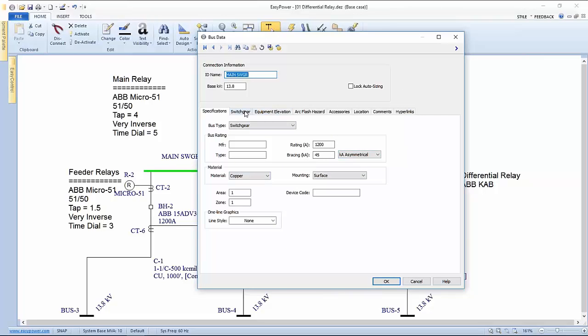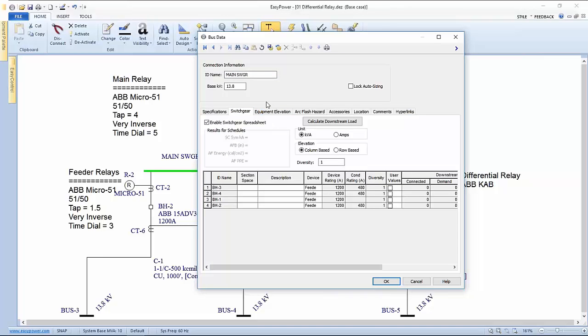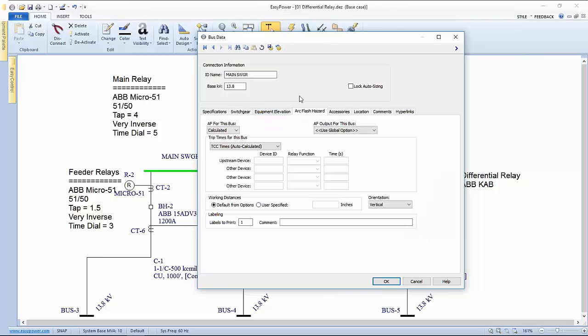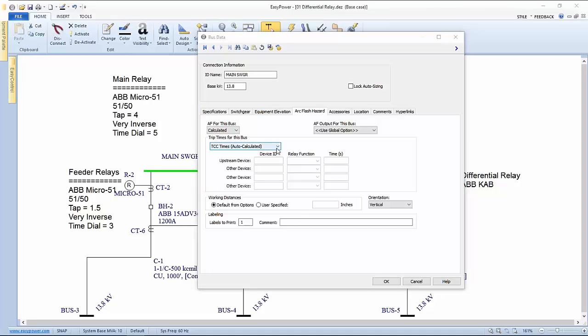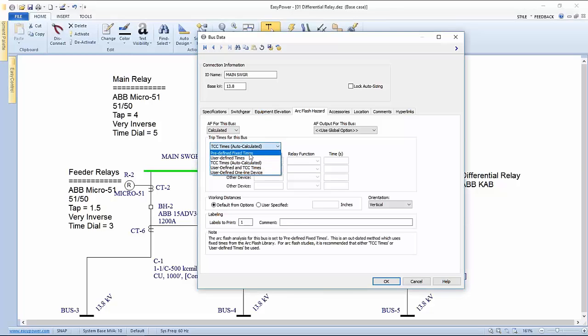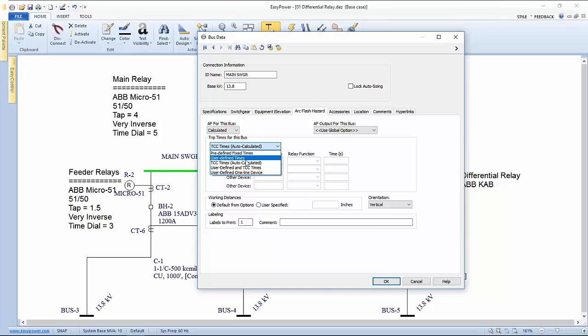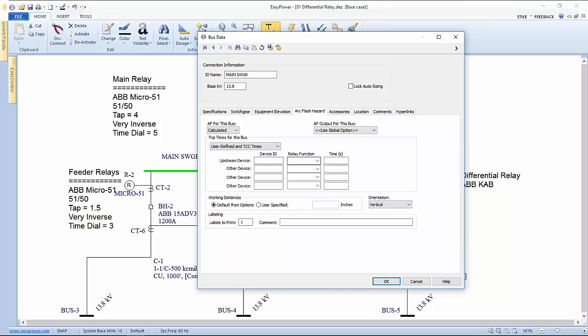When we go into the Arc Flash tab, each element in the system has a data dialog box. When we refer to a dialog box for a relay, we're talking about its dialog box. In this case, we're talking about the dialog box for the main switchgear. It has a number of tabs across the center. In this case, we're talking about Arc Flash. What we want to do in the case of a differential relay is override the global settings. That's what each of these tabs on the individual elements allow us to do. Normally we refer to the global settings for an application to an Arc Flash event.